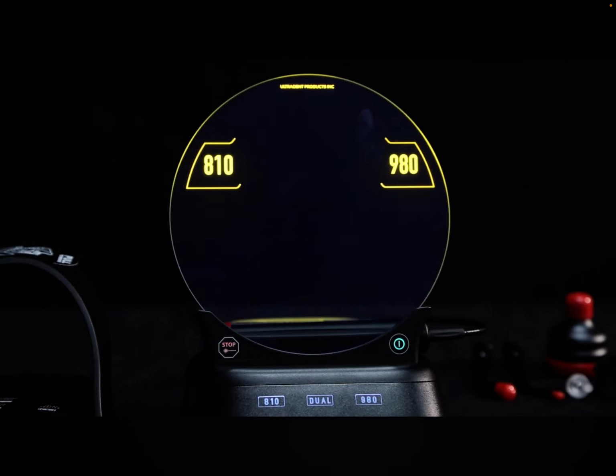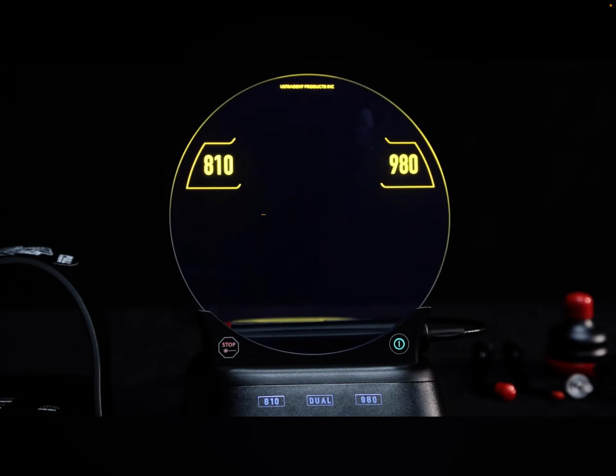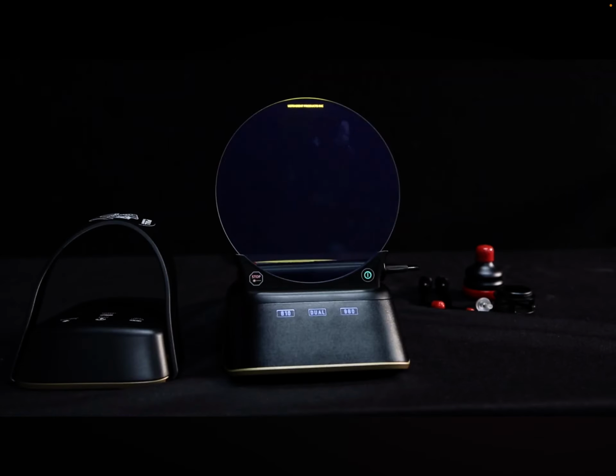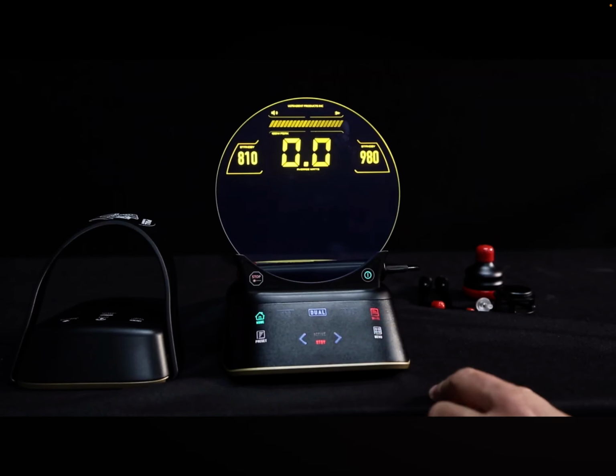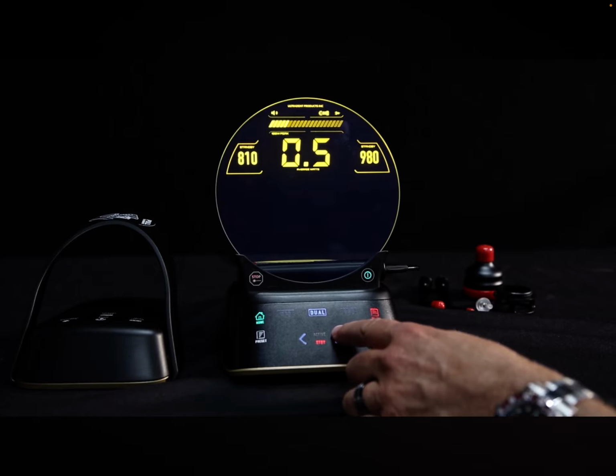The unit then prompts you to choose your wavelength. There are 3 wavelengths available: 810 nanometers, 980 nanometers, and dual wavelength mode combining both. After selecting your wavelength, you can input the average watt setting to start cutting if you know the settings you need to use. Select Active, then depress the foot pedal.